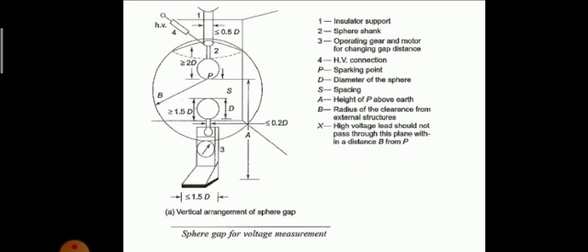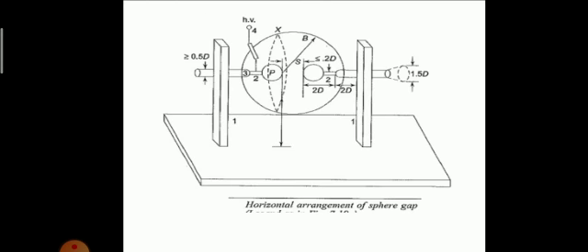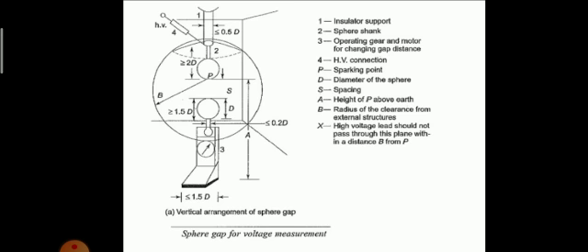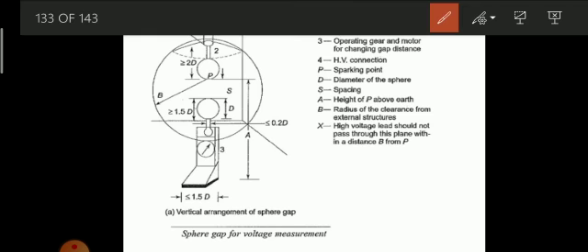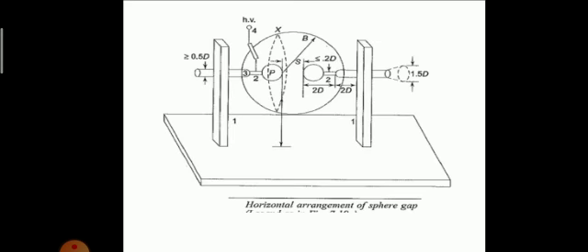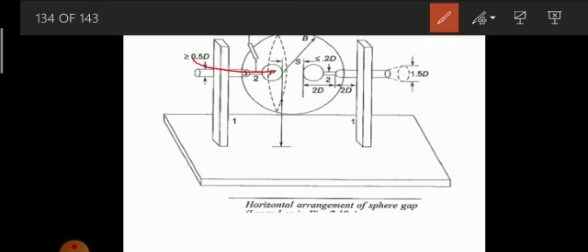So here I'll show you the assembly. Okay, sphere gaps. There are two assemblies. Sphere gaps can be arranged either vertically like this or horizontally like this. Vertically is this with the lower sphere gap, where the lower sphere is connected to ground. Or horizontal sphere gap, with both spheres connected to the source voltage. Either I can connect both the spheres to source voltage or I can connect one sphere to the high voltage source, and the other sphere I'll bring and connect to ground. Now under horizontal, generally we go for horizontal arrangement.